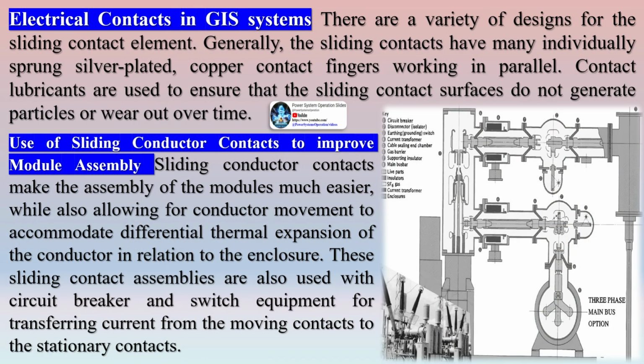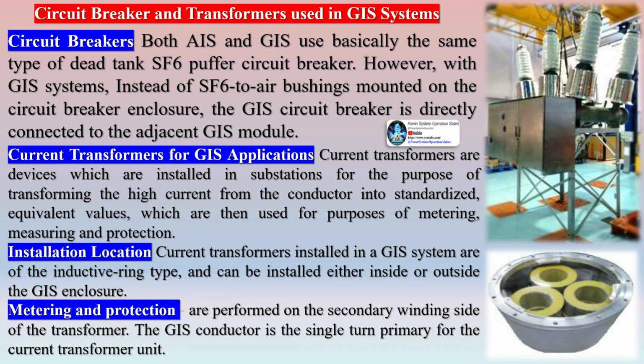Electrical contacts in GIS systems. There are a variety of designs for the sliding contact element. Generally, the sliding contacts have many individually sprung silver-plated copper contact fingers working in parallel. Contact lubricants are used to ensure that the sliding contact surfaces do not generate particles or wear out over time. Circuit breakers, both AIS and GIS, use basically the same type of dead tank SF6 puffer circuit breaker. However, with GIS systems, instead of SF6 air bushings mounted on the circuit breaker enclosure, the GIS circuit breaker is directly connected to the adjacent GIS module.